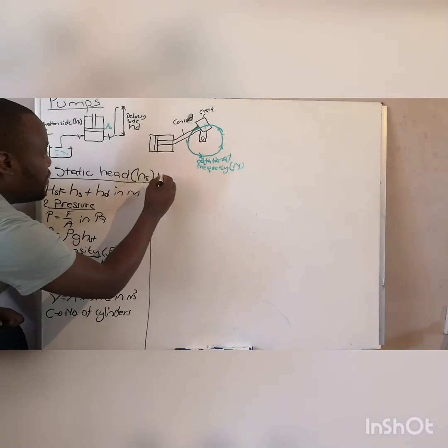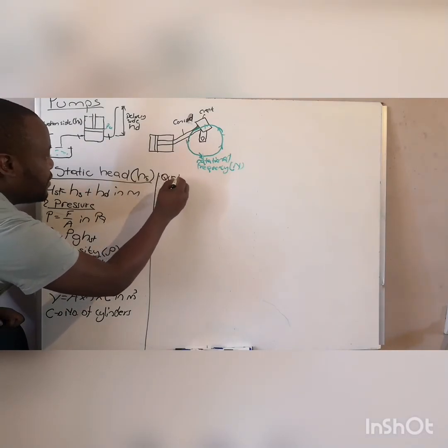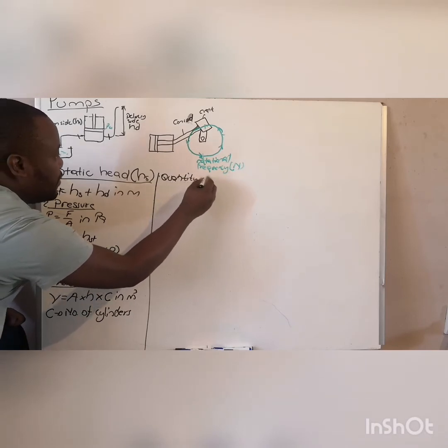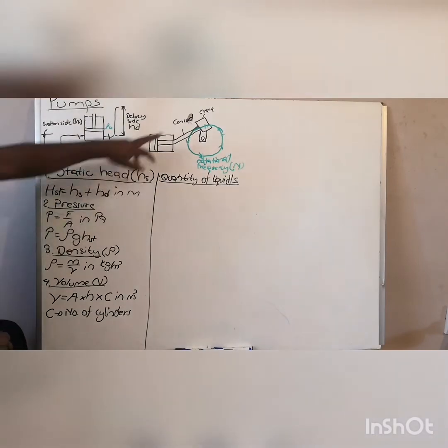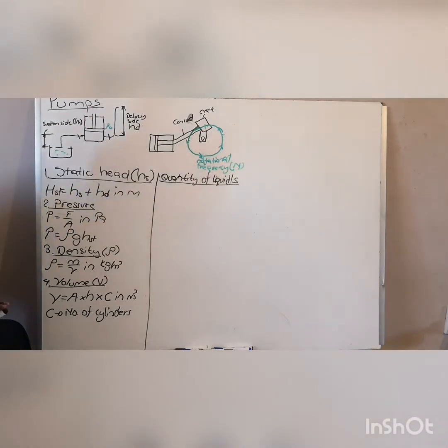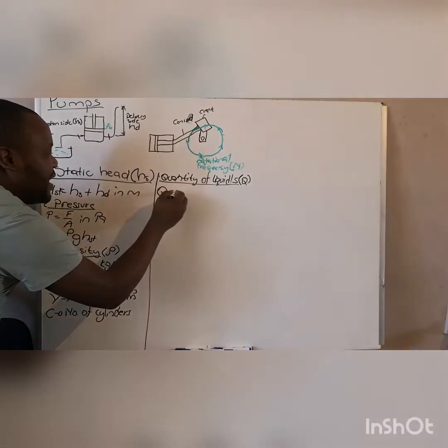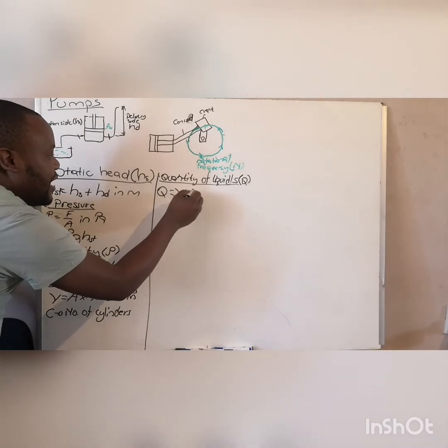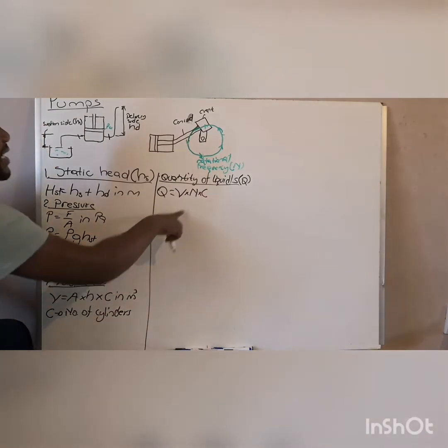The fifth formula is quantity of liquid delivered per second — that is, volume delivered per second. This is where you incorporate the crank, since the crank operates in revolutions per second. To calculate the volume delivered per second, multiply by the rotational frequency n. The symbol used is Q. The formula is Q equals V times n times C, where n is your rotational frequency.